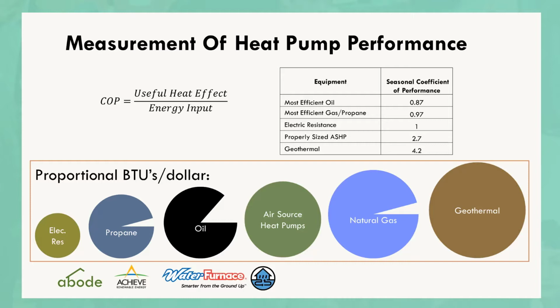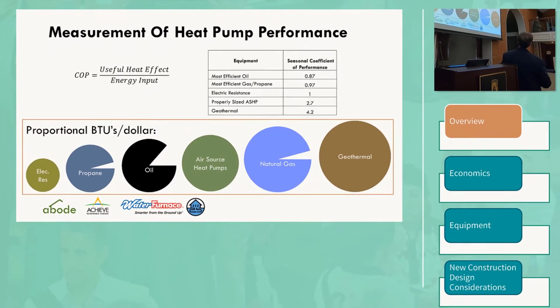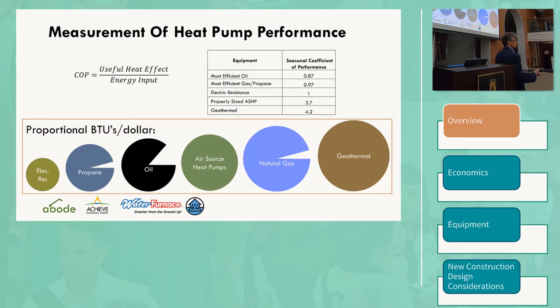If you consider for a moment an electric hot water heater or electric resistance heat, if you put a kilowatt of energy into that electric element, a kilowatt of electrical energy into that element, you'll get a kilowatt of thermal energy. So the COP would be 1 or the efficiency would be 100%. With a fossil fuel system, a portion of the energy always goes up the flue no matter how efficient that system is. So the COP of a fossil fuel system is always less than 1. In the case even of a very efficient fuel oil system, it might be 0.87. Older fuel oil systems could have a COP 0.7 or 0.8. Same for gas or propane systems.